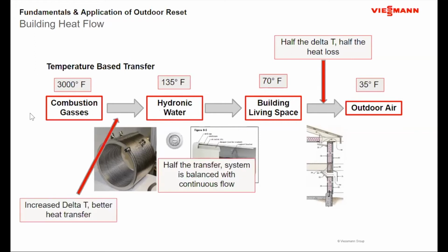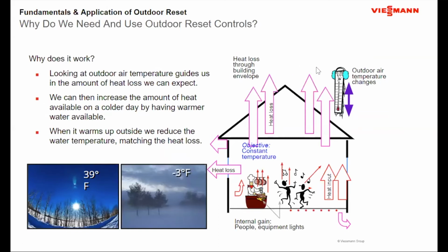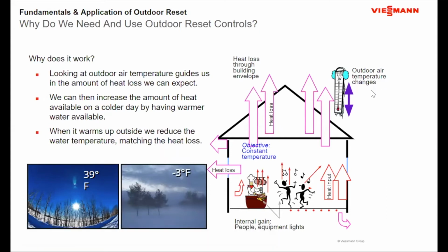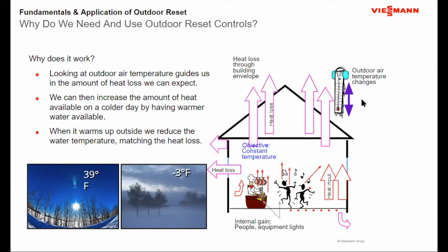The real key is the reset has to be done based on outdoor temperature. And why we're looking at it through the aspect of outdoor temperature is the outdoor temperature really is the major factor in how much loss the building has. So if we can look at the outdoor temperature, as we see the temperature change, we can anticipate and change the amount of heat input into the building so that we stay balanced. So as the outside temperature goes down on a colder day, we increase the water temperature going into the building, and that increased water temperature balances with the higher heat loss that occurs because the outdoor temperature has gone down. Conversely, if it warms up outside, we sense that outside temperature going up.